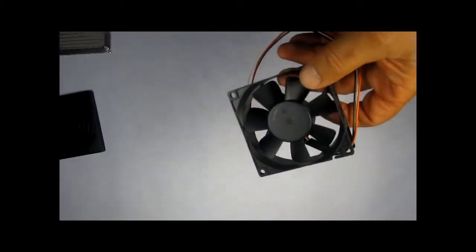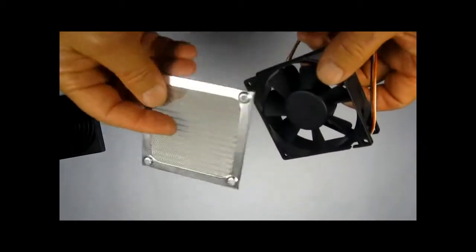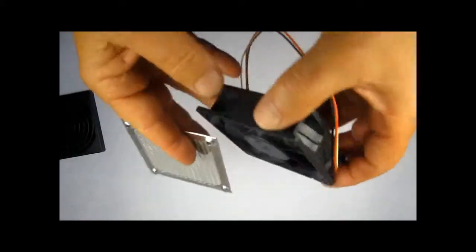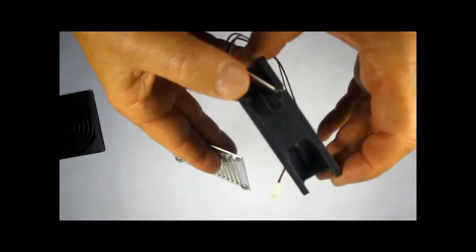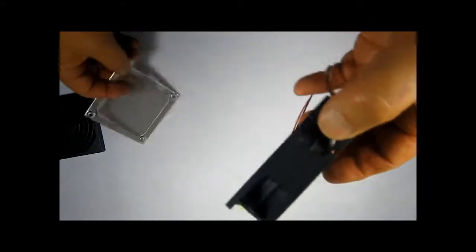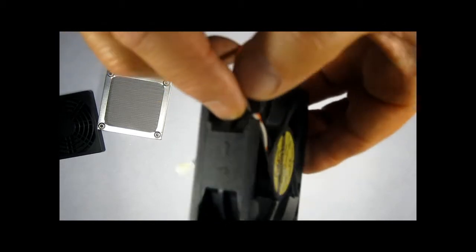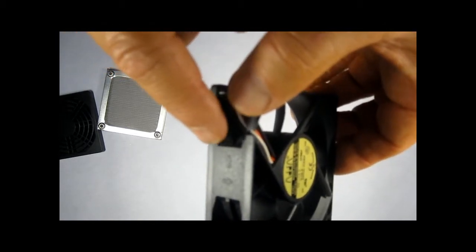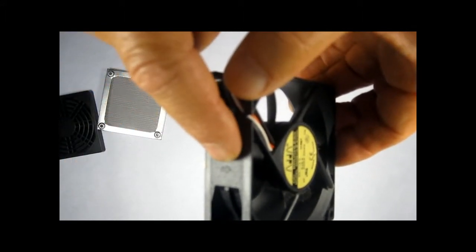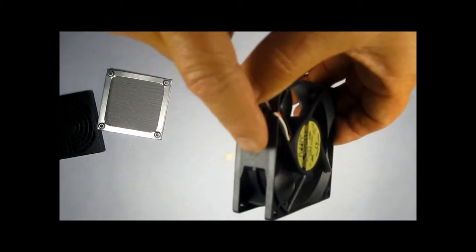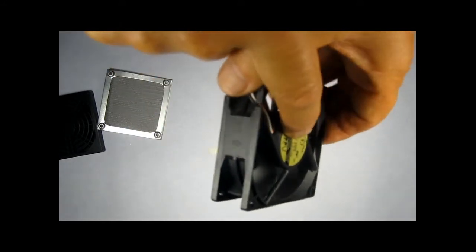So let's talk a little more about the filter itself. Metal filters are just a single piece. You would put that on the inlet side of the fan. Now, what is the inlet and how would we know? On most every fan, you'll see it'll have two arrows. One shows the direction that the blades rotate. The other one shows the direction that the air would go, because when the fan's not working, you have no idea. In this case, the air shows that it comes into this side and goes out this other side.